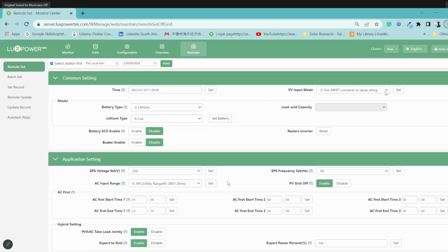The PV input mode, which on the inverter is setting 2, I think. In most cases, you probably can have it set to number 4, which is 2 MPPTs connected to different strings, string 1 and 2. That's in most cases. I'll see how you guys have set it up, which is fine. Just make sure that your connectivity on the panel side is correct, and then you will set that over there.